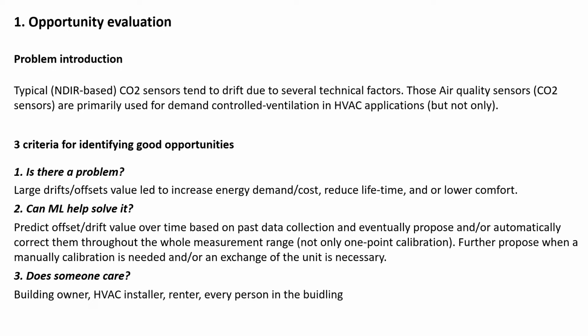Let's start with the opportunity evaluation and spend some words about the problem itself. CO2 sensors tend to drift due to several technical factors. These CO2 sensors, air quality sensors, are primarily used for demand control ventilation in HVAC applications. So is there a problem? Yes, because large drift offset values lead to increased energy demand cost, reduced lifetime of the product, and/or lower comfort.